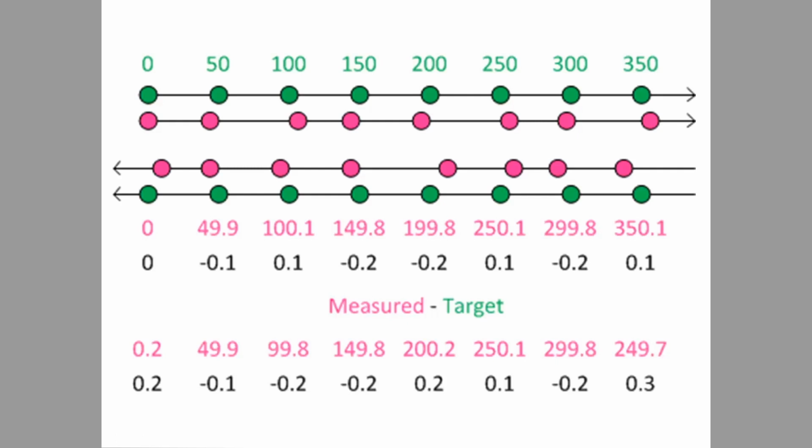The trick starts showing up when you start doing multiple runs. So let's say we're going to do 3 bidirectional runs, 6 runs total. The problem is that we start getting that little bit of noise from repeatability at x equals 0. So what that ends up meaning is that when we start looking at our comp values, the x0 in the positive direction, where we zero the laser, starts getting small numbers.